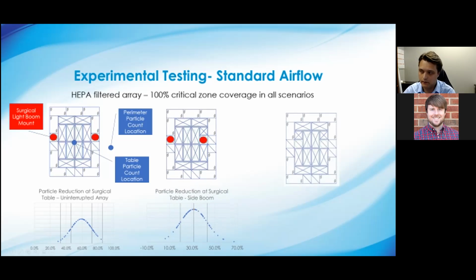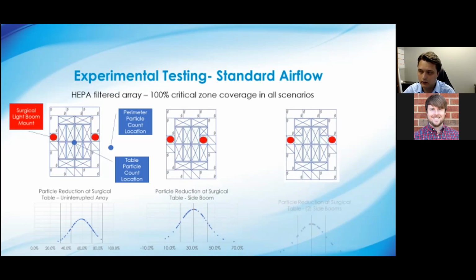You take it one step further and move both booms in to the same distance from the table, still not encroaching on that 100% critical zone coverage. You've effectively eliminated any protection that laminar flow is providing to the patient. 0% of particles in this space are getting stopped from reaching that patient, even though you're exceeding ASHRAE in every possible sense.